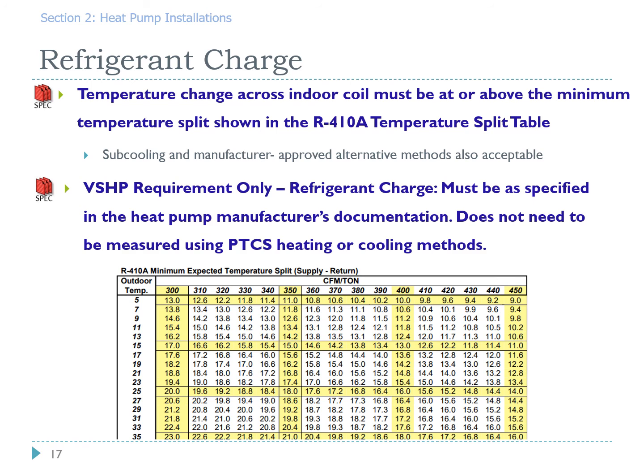In summertime, or any time that the outdoor temperature is above 65 degrees, subcooling is used, or a manufacturer's method such as approach or superheat. Note that variable speed heat pumps do not need to be tested using these methods, but they must meet the manufacturer's specified charge method.